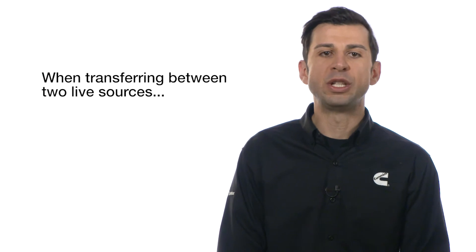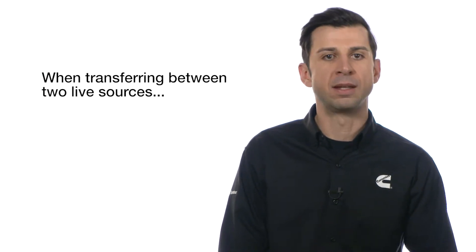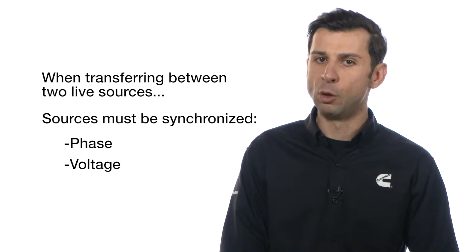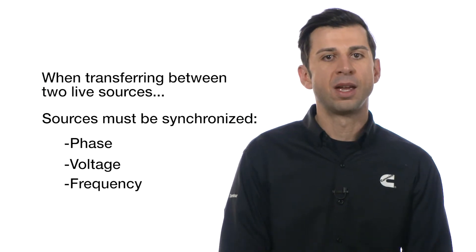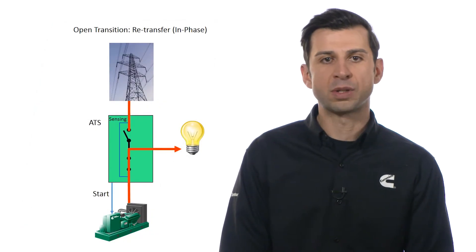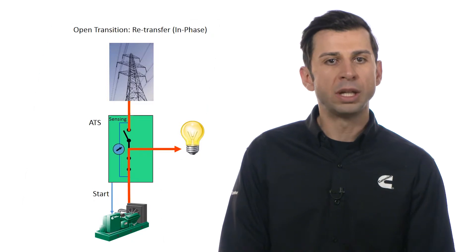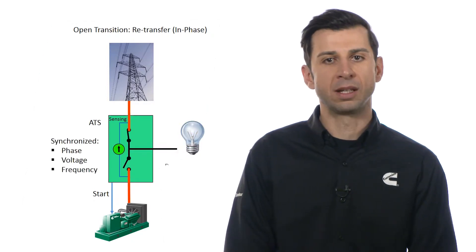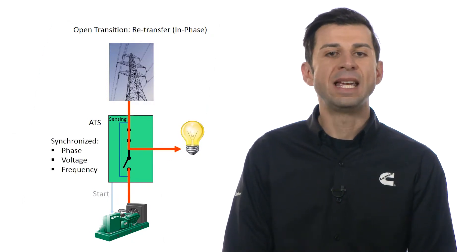When transferring between two live sources, it is important that the sources are in sync with each other: phase, voltage, and frequency. The transfer switch will monitor both sources and allow transfer only when the live sources are in sync. This is known as in-phase transition.